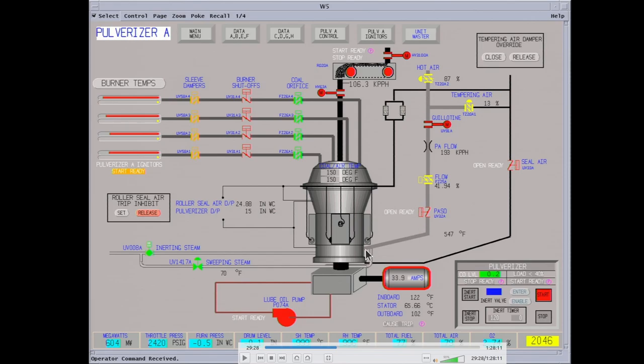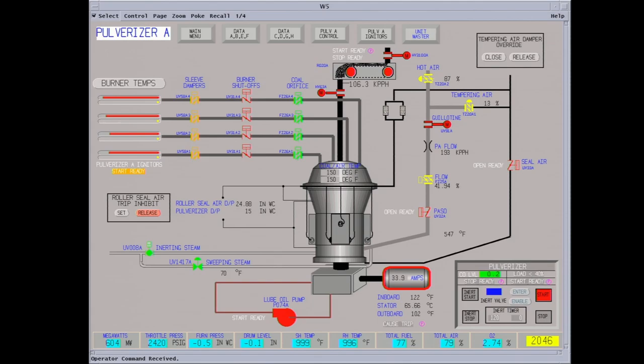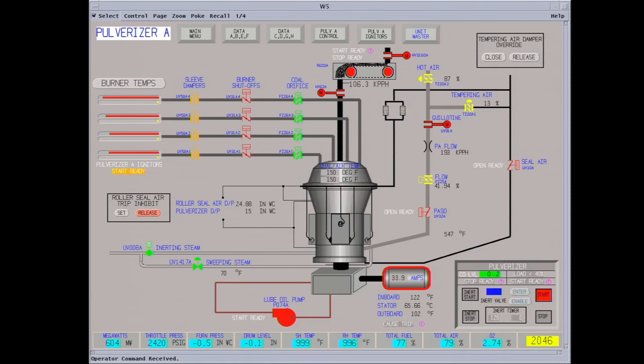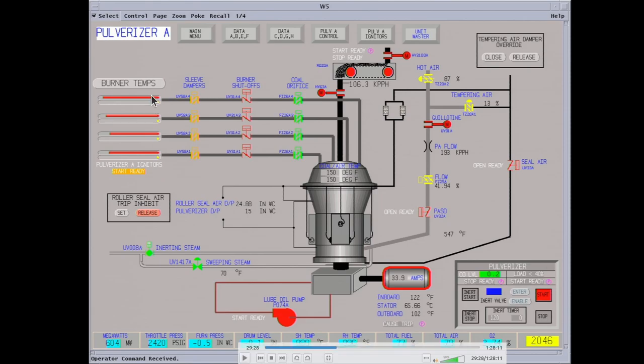So you're feeding hot air and cold air together — depends on the amount of moisture in the coal and how much drying it has to do. You've got your guillotine damper and your main flow control damper — you try to maintain the air flow versus your coal flow. The coal silo sits up here. You have your outlet valve, here's a coal feeder — it's a gravimetric feeder. It maintains a certain amount of coal on the belt and changes belt speed to change your coal feed. Coming out, you have your burner shutoffs. These sleeve dampers are part of the combustion control — they control how the air is being fed in around the burners. You have your igniters and flame scanners.